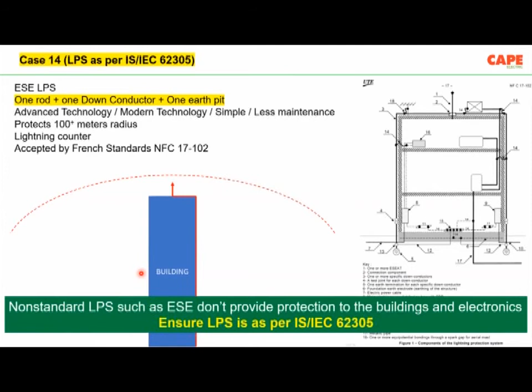Early streamer emission is not a magic device which attracts lightning from 100 meters and sends it directly to the earth through one down conductor. This one rod, one down conductor, one earth electrode is actually a foolish idea. The standard recommends a proper equipotential bonding system. The French code explains a proper equipotential bonding system. Whereas in a lot of places, the rod is there, one down conductor, one earthing. Items 2 to 18 are missing. Only one rod, and most of the time with long wires. So you forget it, it won't work.